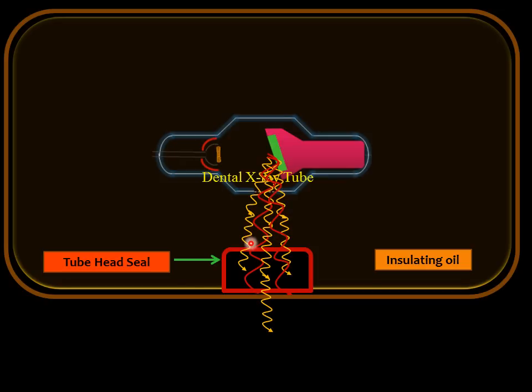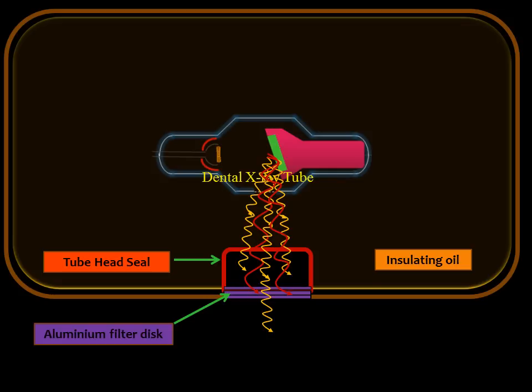The aluminum disc filters the low energy long wavelength x-rays and allows only the short wavelength high energy x-rays to pass through the x-ray tube head. At 70 kvp, a thickness of 1.5 millimeters of aluminum filters are used, and above 70 kvp we use 2.5 millimeter thickness of aluminum.